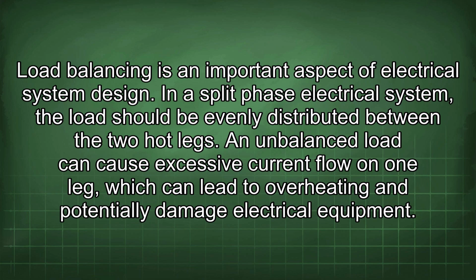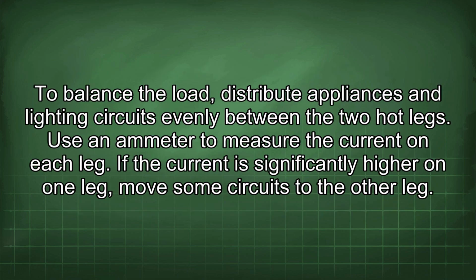Load balancing is an important aspect of electrical system design. In a split-phase electrical system, the load should be evenly distributed between the two hot legs. An unbalanced load can cause excessive current flow on one leg, which can lead to overheating and potentially damage electrical equipment. To balance the load, distribute appliances and lighting circuits evenly between the two hot legs. Use an ammeter to measure the current on each leg. If the current is significantly higher on one leg, move some circuits to the other leg.